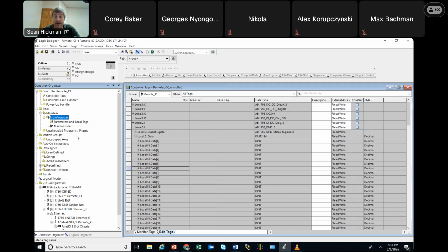That way, when you pull it up, the first thing you do, whether you're using them all or not, you have all your inputs mapped and all your outputs mapped, and then you don't have to do it every time. If you don't do it, every time you start a program for me, you're going to have to map your inputs and outputs by creating an input mapping sub, because inputs got to be mapped from here on out. It's up to you, but you might want to throw that into your template. Okay.